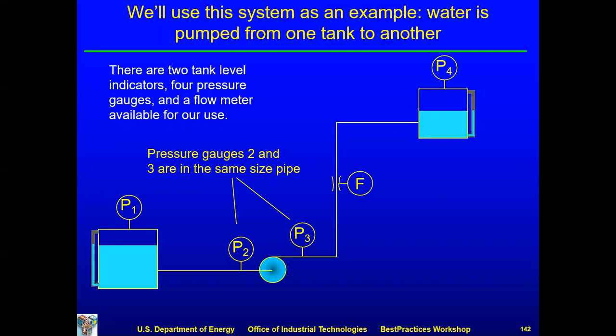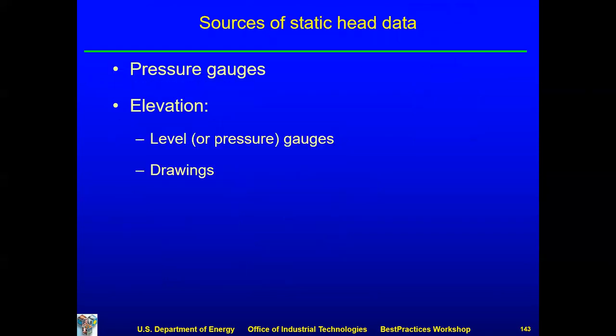Okay, so here's an example. What do we got? We got a couple of tanks. We got one right behind us, which is fairly small, fairly low. And then we're going to pump up on the hill. We have the potential to have gas overpressure, P1 in the suction tank, and P2 or P4, which would be in the discharge tank. And so we'll throw some numbers in this. We're also showing suction and discharge gauges on the pump and a flow meter. And for this little example, we assume that we have the same size pipe. Because if we have different size pipe, then we've got a change in velocity head from suction to discharge. So at least right here, we're just going to assume we've got the same pipe on both sides. Okay.